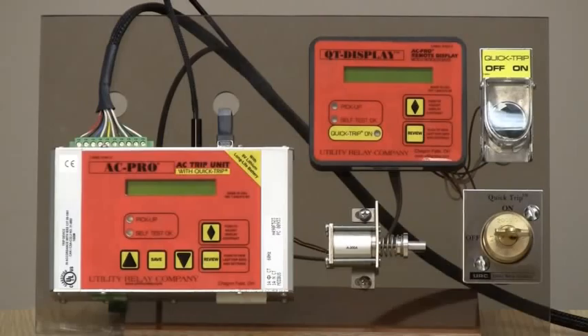The quick trip display gives you all of the functionality of the AC Pro except for commissioning the unit and clearing the trip counters, all without opening the cubicle door. The quick trip display allows you to view the real-time ammeter monitoring and review the AC Pro settings and last trip data. This is done using the same process as the AC Pro itself.